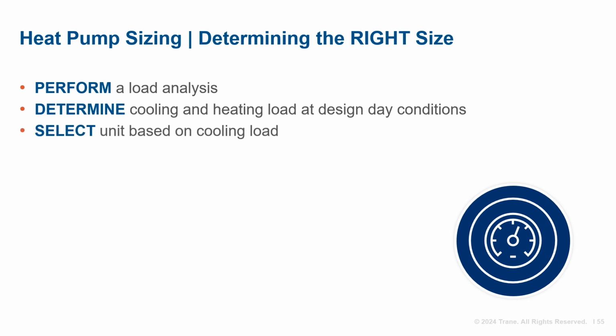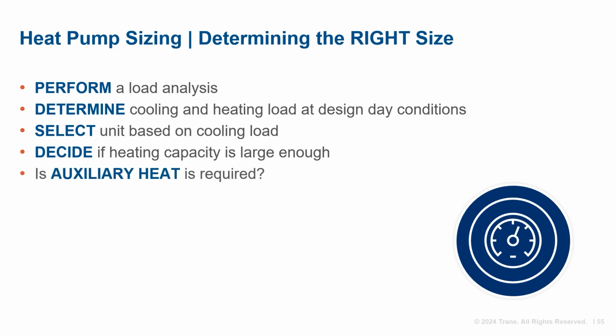Next, select the rooftop unit at the design cooling load condition. Using information from the manufacturer, you can now determine the net heating capacity of the selected unit at varying ambient temperatures. Last, decide if the heating capacity provided by the unit will be enough to cover the required heating load. If not, auxiliary heat will need to be added. In the next few slides, I'll show an example of how to demonstrate the process of sizing a heat pump unit. And we'll wrap up with some additional tips to assist you in accurately determining the right size for your heat pump.